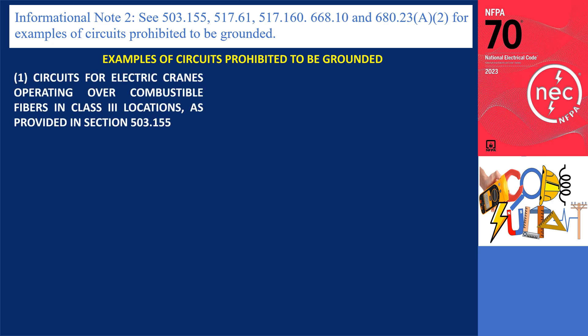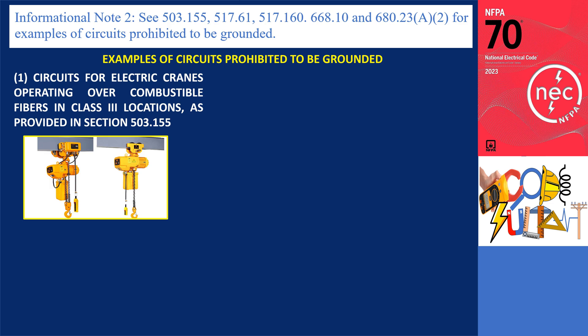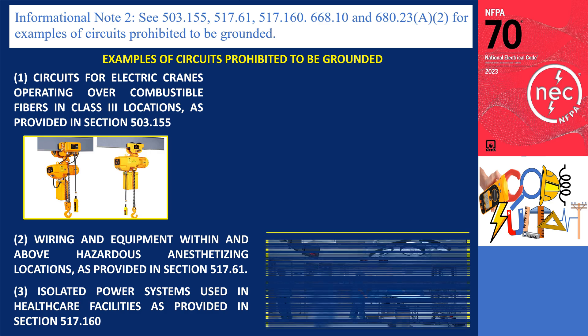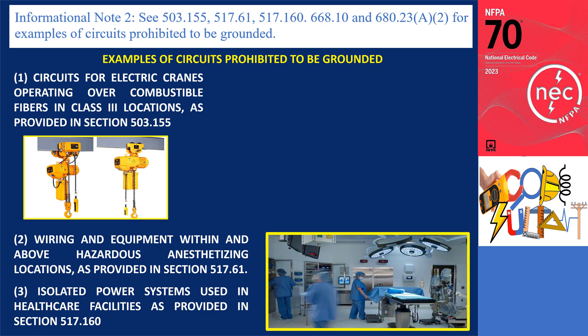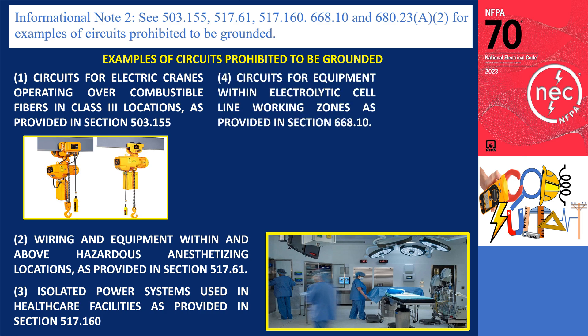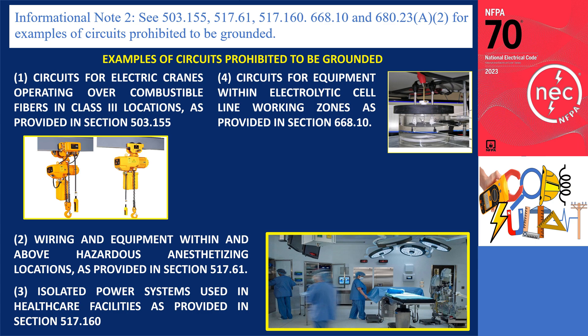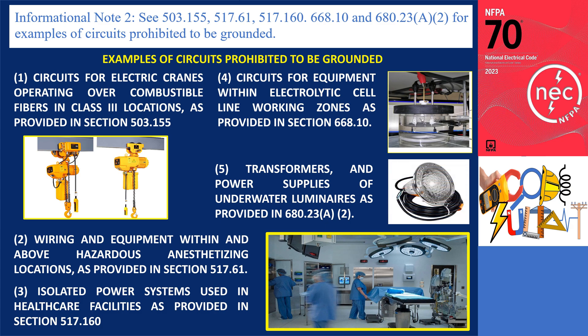Additionally, in informational note number two, circuits covered in the following sections are prohibited from being grounded: 1. Circuits for electric cranes operating over combustible fibers in class three locations, as provided in section 503.155 — the purpose is to eliminate sparks or hot particles due to a phase-to-ground fault. 2. Wiring and equipment within and above hazardous anesthetizing locations, as provided in section 517.61. 3. Isolated power systems used in healthcare facilities, as provided in section 517.160. 4. Circuits for equipment within electrolytic cell line working zones, as provided in section 668.10. 5. Transformers and power supplies of underwater luminaires, as provided in section 680.23(A)(2).